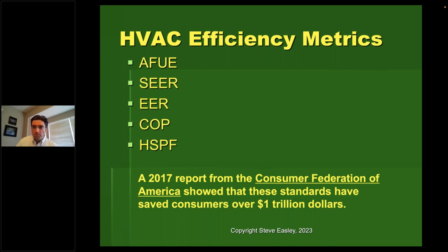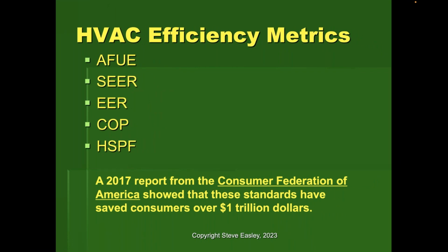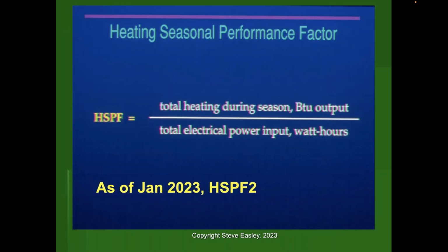Okay, great. With regards to the way we measure the efficiency of this equipment, gas equipment, we measure through annual fuel utilization efficiency. Air conditioners, we measure that through seasonal energy efficiency ratio. And sometimes we use EER. For those of you out in the West and the Southwest in particular, where you have very hot temperatures, EER, or EER2, is a much better metric to measure the overall performance of your air conditioner, for example. Coefficient of performance is another way that we measure that, and I'll talk about that. And then heating seasonal performance factor and heating seasonal performance factor 2, as a result of January 1, we've had some significant changes. So the heating seasonal performance factor is a big metric that we use to measure the performance of heat pumps, and it's simply the total heating season BTU output divided by the electrical power input in watt hours. And then as of January of this year, we now have what we call heating seasonal performance factor 2.